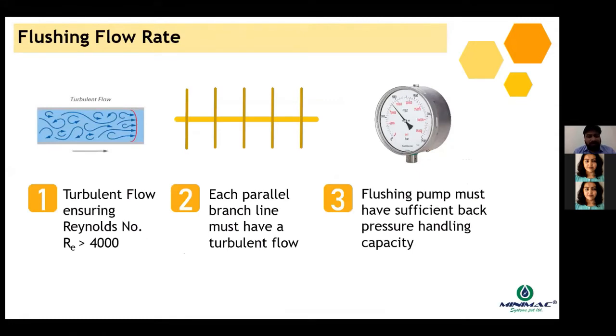The first one, flushing flow rate. We have already discussed the Reynolds number. It has to be more than 4,000. The second one, we had briefly touched upon while we were discussing one of the myths. As you can see, this is a pictorial representation of a piping network where the central line is one of the largest diameter pipelines, but the branch lines are much narrower or thinner. Now, when you calculate the flushing flow rate across each of these branch lines and add them up, you would land in a situation where the flushing flow rate calculated as per each of these branch pipelines would certainly come more than the flushing flow rate calculated through just the main header pipeline, which is at the center of this network.